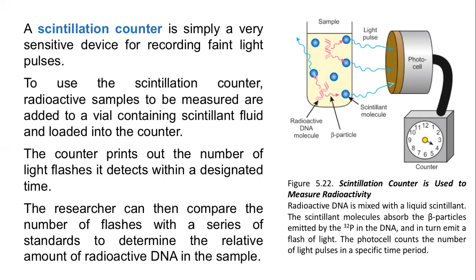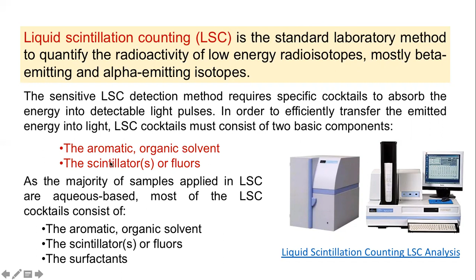The liquid scintillation counter is a standard laboratory method to quantify the radioactivity of low energy radioisotopes, especially beta emitting and alpha emitting isotopes. And this is the instrument that you can see over here. The light sensitive liquid scintillation counting method requires a specific scintillation cocktail of substances which helps to absorb the energy, which can be detected as light pulses, and they mainly include aromatic organic solvents and scintillators or fluors, as we call them.